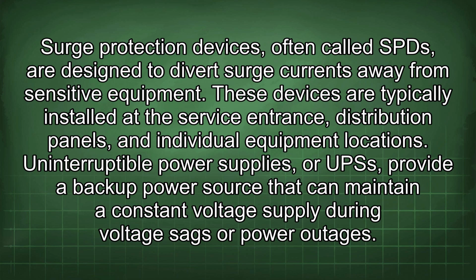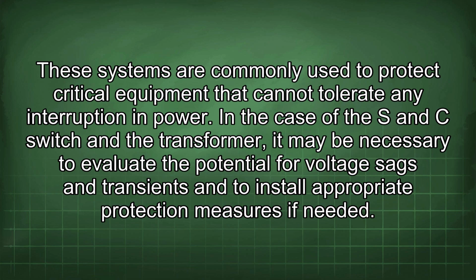These devices are typically installed at the service entrance, distribution panels, and individual equipment locations. Uninterruptible power supplies, or UPSs, provide a backup power source that can maintain a constant voltage supply during voltage sags or power outages. These systems are commonly used to protect critical equipment that cannot tolerate any interruption in power.